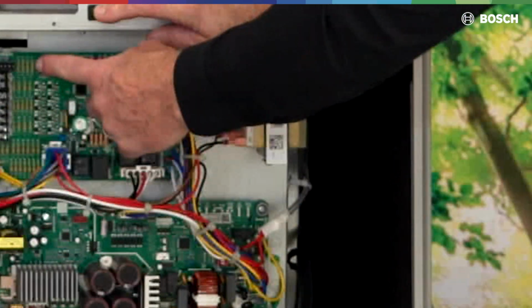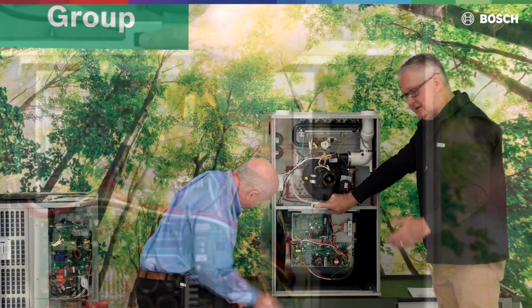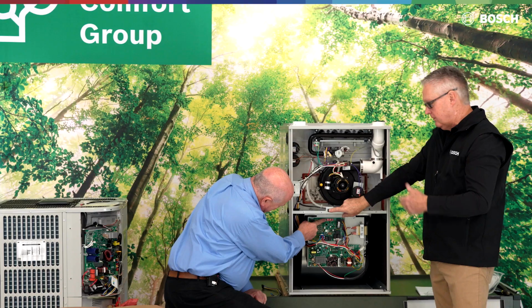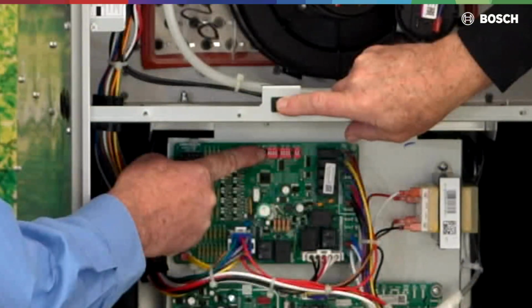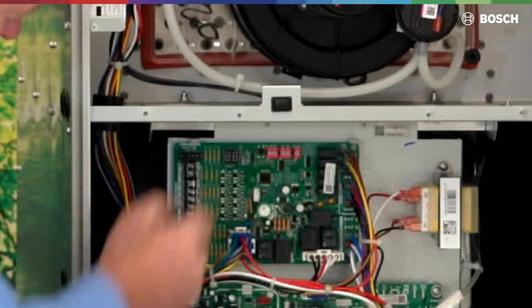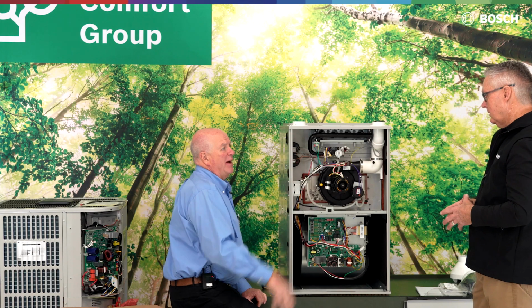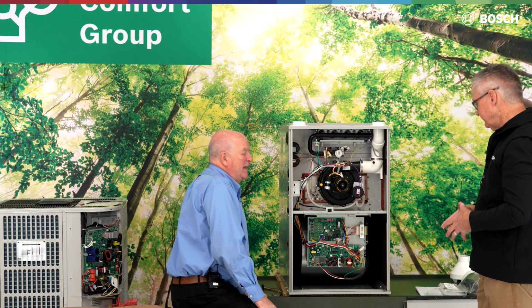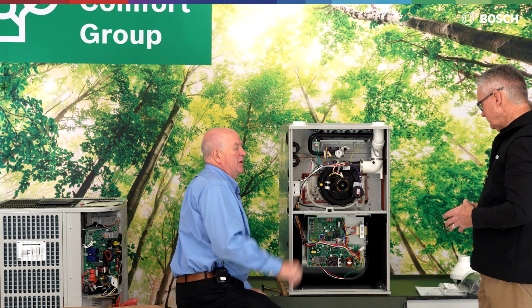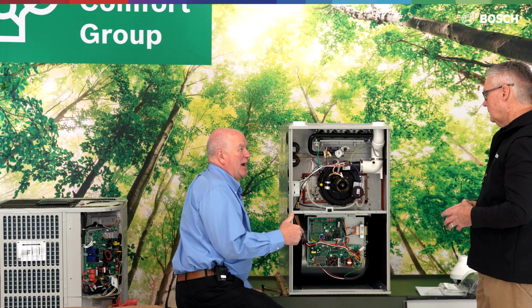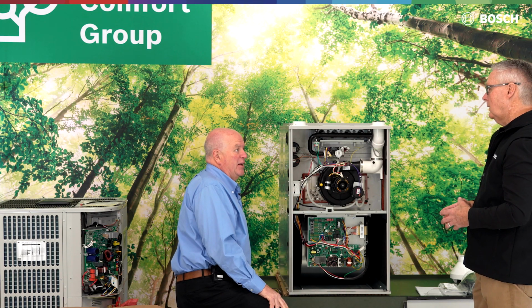And I now get to push a button here that allows me to see the last 10 fault codes. That button is right here beside the dip switches. It's going to tell you the last 10 fault codes, and it truncates, I guess, so after the 11th one, it wipes out. The first code is the most recent one. So you hit the button the first time, it is the most recent fault code that you get.